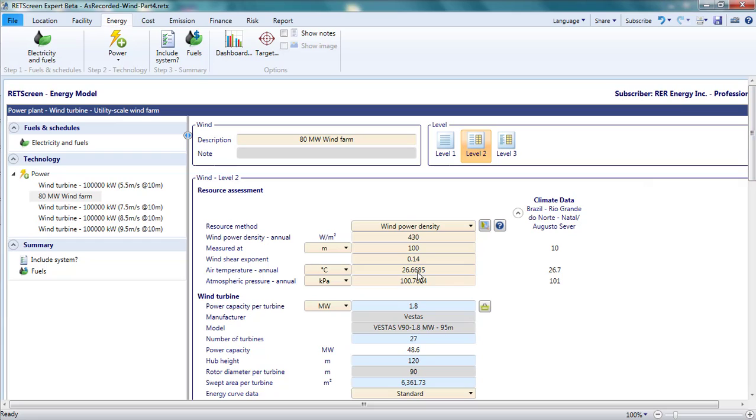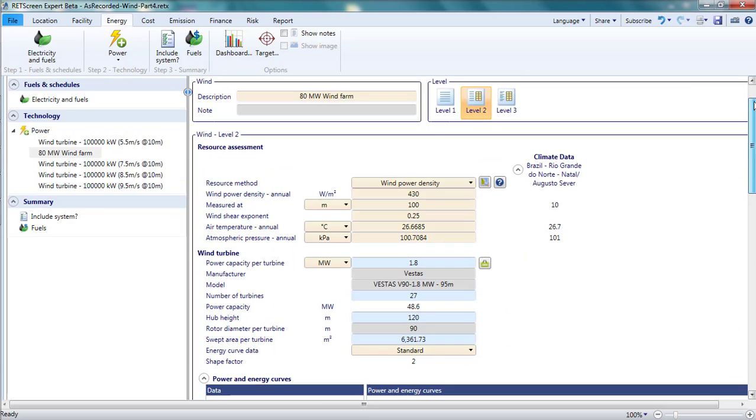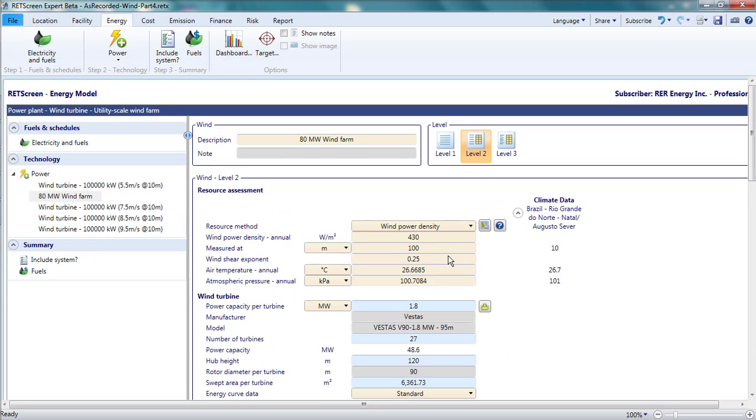This is for a wind shear exponent of 0.14. If the wind shear exponent were 0.25, the capacity factor would be 35%, since the wind speed is increasing by a larger amount for a given increase in height. Would it be reasonable to enter 0.25 as the wind shear exponent? After all, our project looks better that way. Unfortunately, we are not at liberty to specify whatever we want.